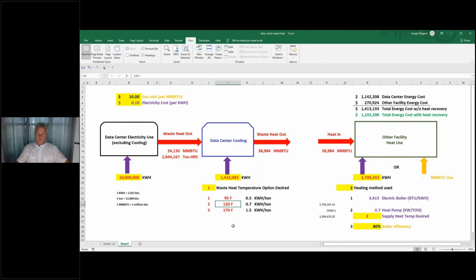Suppose, however, you used a heat pump and you said, I want the water coming out of my chiller to be, instead of 95 degrees to go to a cooling tower, 120 degrees, so I could use it to provide hot water for my buildings and restrooms. Well, the heat pump would take about 0.7 kilowatts per ton to give you 120 degree hot water instead of 95. And if you wanted much hotter water, such as Stanford uses, because we have a lot of buildings used to receiving 160 or 170 degree water, your heat pump would consume about 1.5.